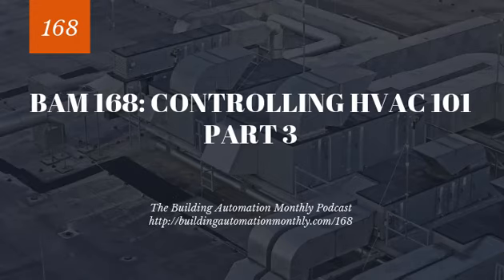All right. So as I mentioned, we have cooling tower controls. Now, with cooling tower controls, when the condenser water is at or below set point, we can bypass the tower, disable the fans, and just run the water in a loop. Now, as the temperature rises, we will typically have the flow go fully through the tower, okay? And this means through the basin of the tower.